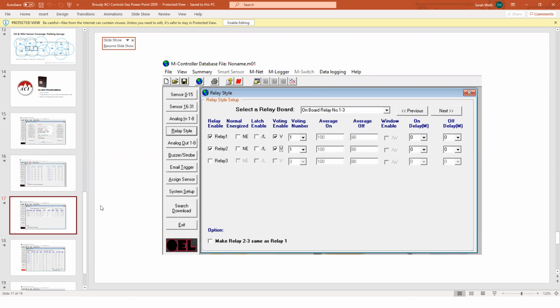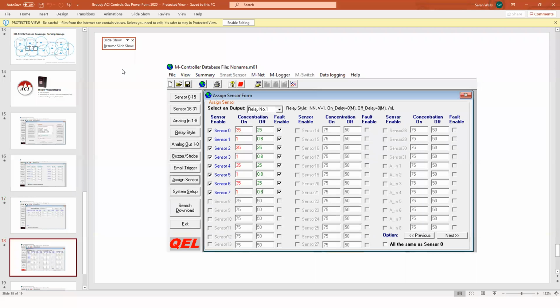And then when we go to the next page, here's where you're assigning the sensors to the relay. You're determining what the on concentration is and what the off concentration is. And it doesn't matter whether it's a CO or an NO2, you can put those different concentration levels to one relay so that if that first trip level is reached by any of the sensors, that relay will trip and turn on the fan and start venting air. This is a really quick and easy way to do it.